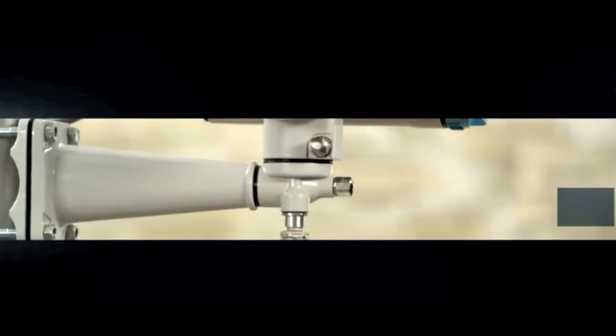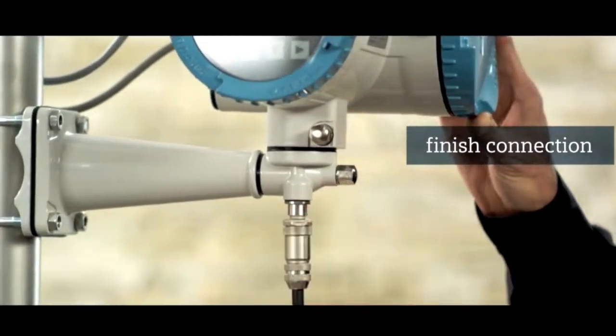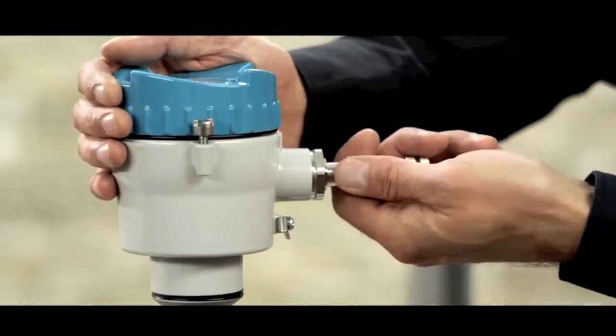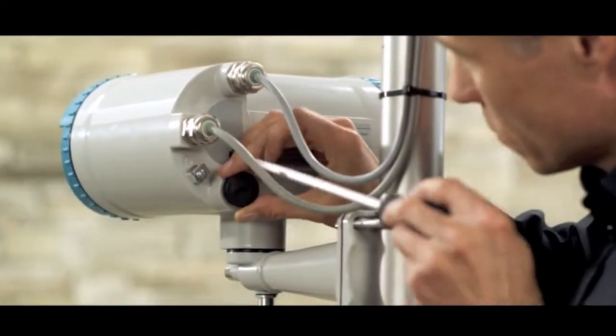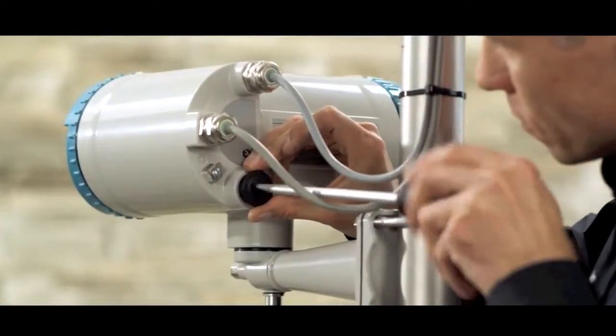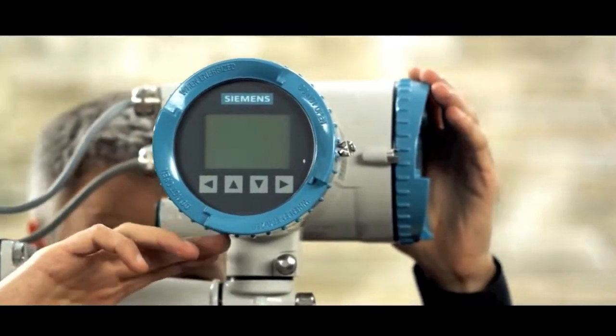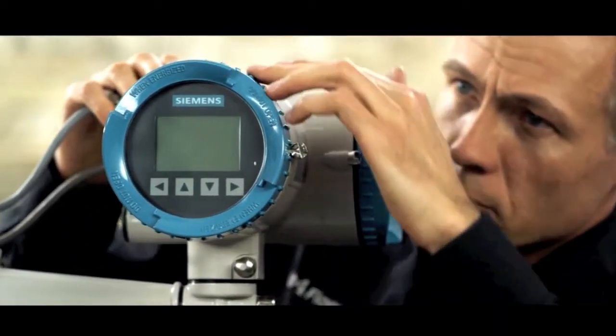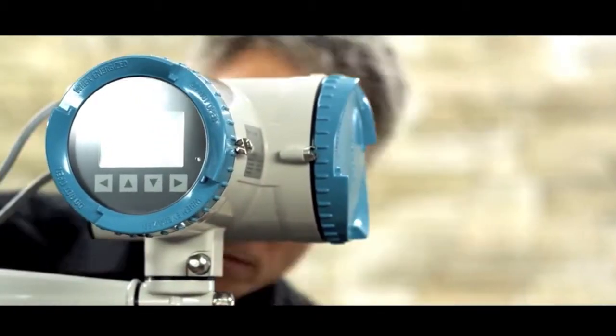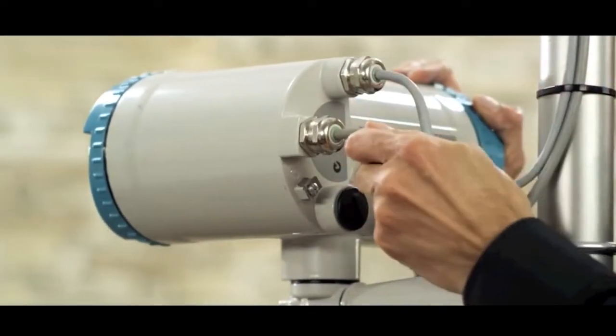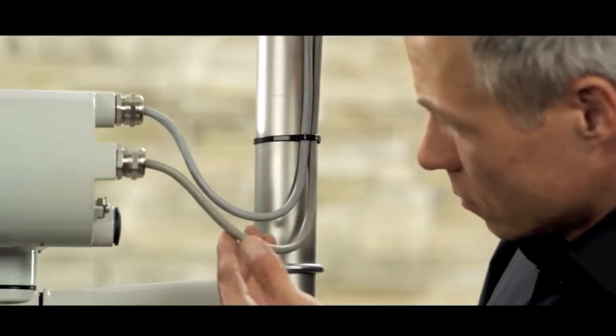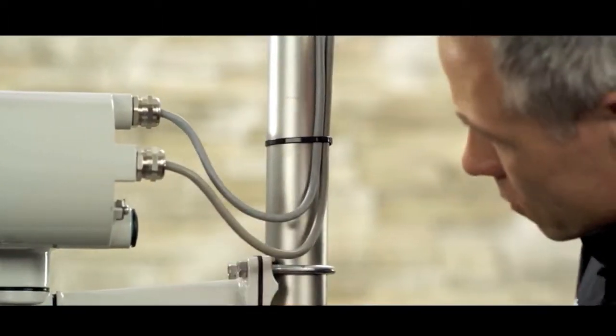Finally, check each cable to ensure that the connections are clean and solid. Screw the blind plugs into any empty cable inlets. Check that the O-ring of the display is correctly positioned. Make sure no moisture can get inside the electronics housing. You can use a drip loop to prevent water droplets from penetrating the cable inlet.